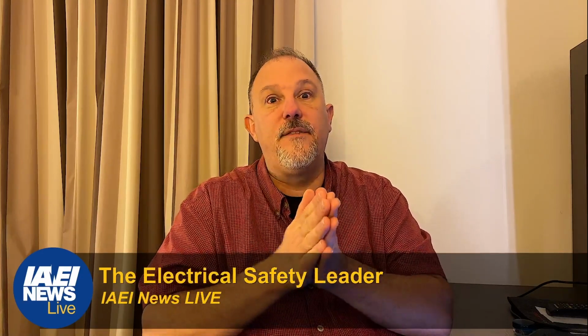And then they do a dynamic voltage withstand test. Because, again, you want to make sure that as you're putting these products through tests, you're subjecting them to some harsh activity. Then you want to do some validation that there's no dielectric breakdown, no chance of something faulting to another conductor internal to that unit. And how you do a dielectric test is you impress a very large voltage on it. So be mindful of that.